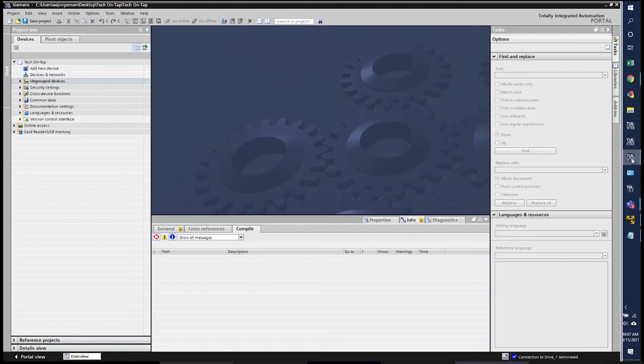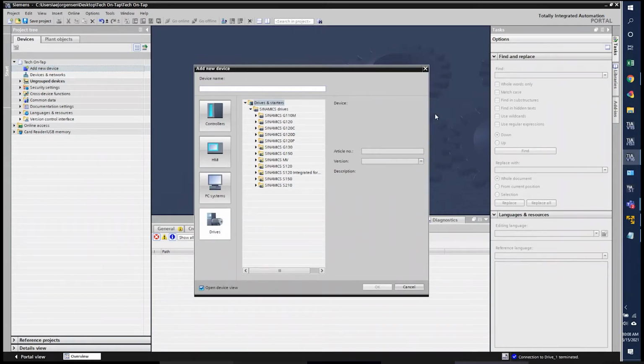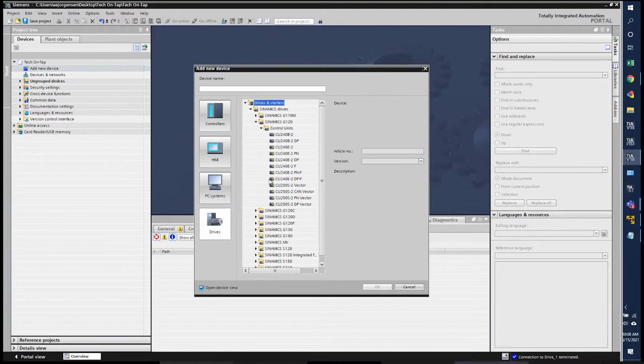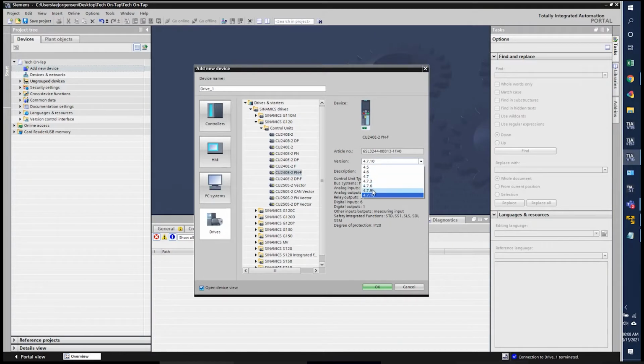So first things first, we need to actually commission the drive. So we need to add the device to our portal project. In this case, we have a G120, a CU240E-2 PN-F, and it's version 4.7.9. You can verify the firmware version using either the Online and Diagnostics tab in Portal, or if you have an operator panel on the drive, you can verify on there in the Extras tab.